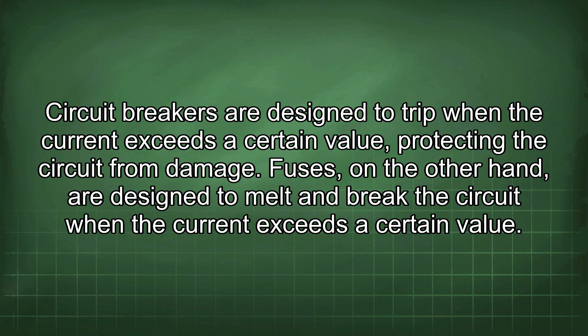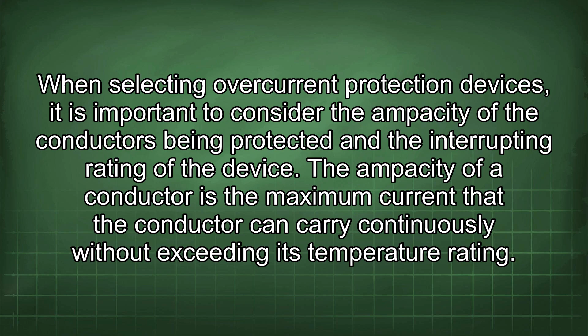When selecting overcurrent protection devices, it is important to consider the ampacity of the conductors being protected and the interrupting rating of the device. The ampacity of a conductor is the maximum current it can carry continuously without exceeding its temperature rating. The interrupting rating is the maximum fault current the device can safely interrupt.